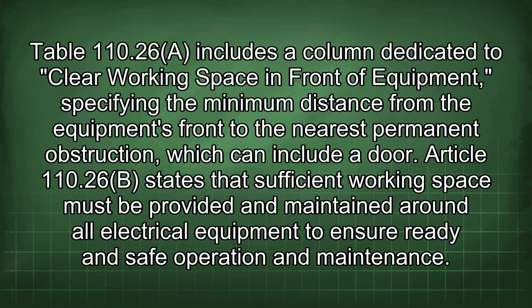Table 110.26(A) includes a column dedicated to clear working space in front of equipment, specifying the minimum distance from the equipment's front to the nearest permanent obstruction, which can include a door.